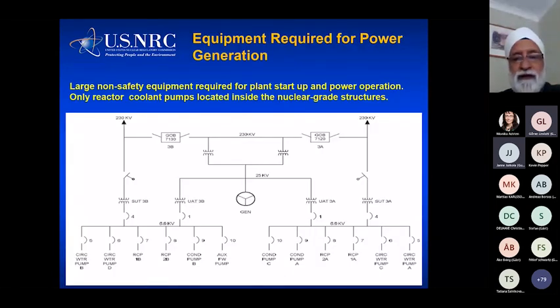So typical nuclear power plant design, connected at 230 kV to the grid system. We have the breakers that isolate the plant from the grid, the generators, and we have the transformers that are all connected to the grid and perhaps vulnerable to E1 because they're outside, E2 because of the lightning effect that can strike on the transmission lines, and E3 because of the connection to the long transmission lines. So the equipment that we are interested in is the interface between the grid and the nuclear power plant. All that is exposed to the EMP wave.